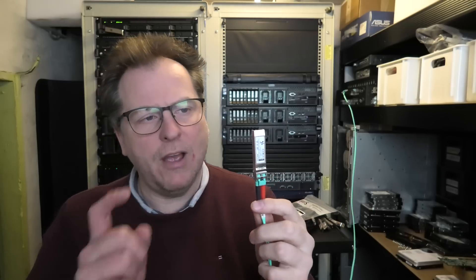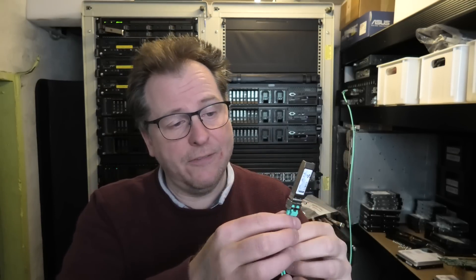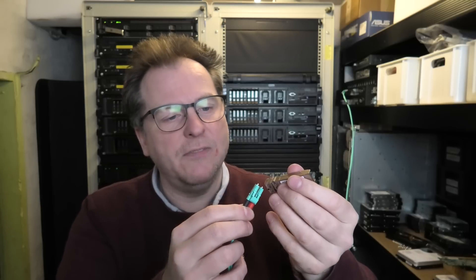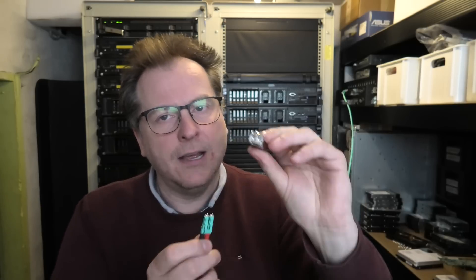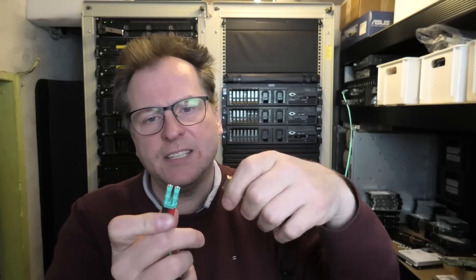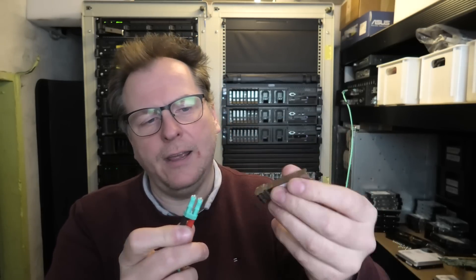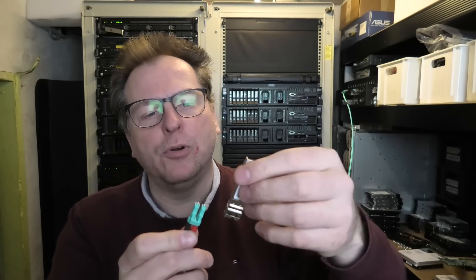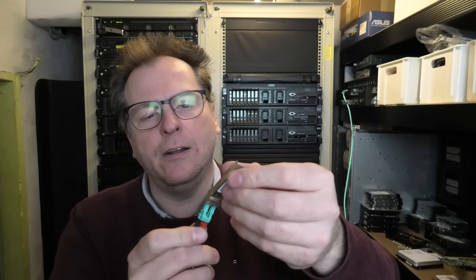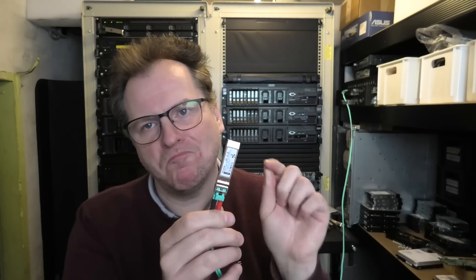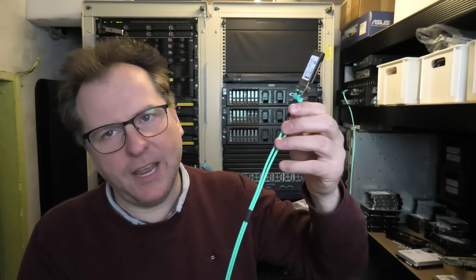A connection like this becomes very complicated. There are multiple ways this can fail on you. You have an SFP in both ends, you have no less than four fiber optic connections that need to be very clean, and also this inside of here needs to be very clean. That becomes dirty. If this is dirty and you put it in here, guess what becomes dirty? That one. Plus the cable is fragile. There is nothing but trouble here.